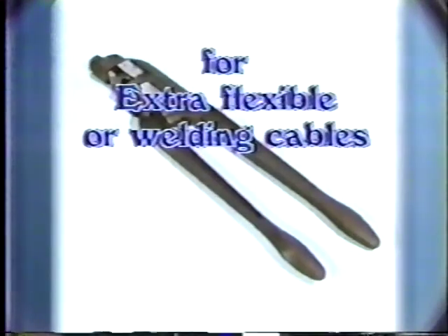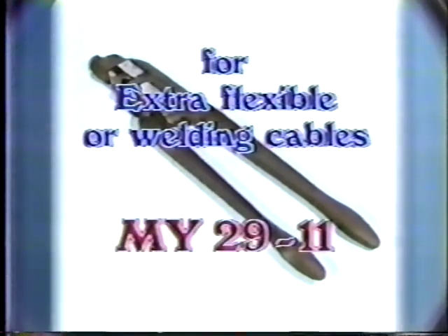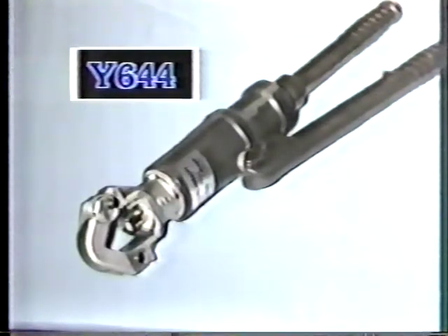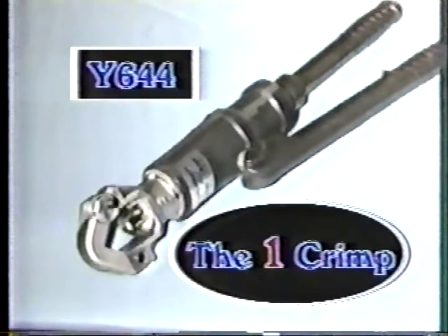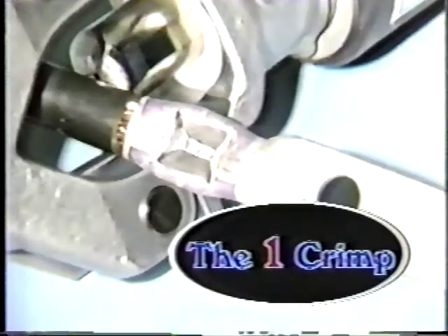The MY29 tool is also available in a version to accommodate extra flexible or welding cables. It's called the MY29-11. To provide quality installations at a lower installed cost, Burndy Engineering developed the Y644 tool. We call it the one crimp because only one crimp is required to make UL and CSA listed installations on a wide range of conductors and connectors.